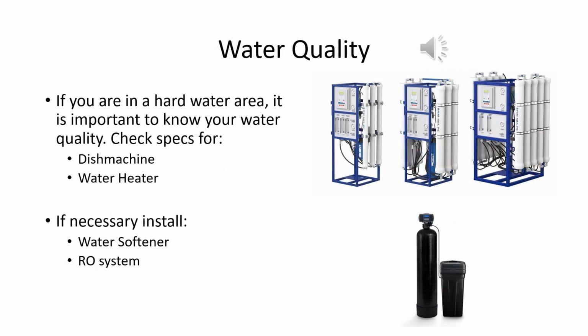When commissioning a hot water system, it is particularly important to know the water quality at your facility, as hard water can lead to a whole host of problems for many pieces of equipment. At the water heater, it can lead to cracked heating elements and flame diverters. At the dish machine, it can cause cracked elements and plugs in the exhaust system. This is especially problematic for heat recovery dish machines as their heat exchangers can foul, which can prevent the machine from meeting its final rinse temperature.